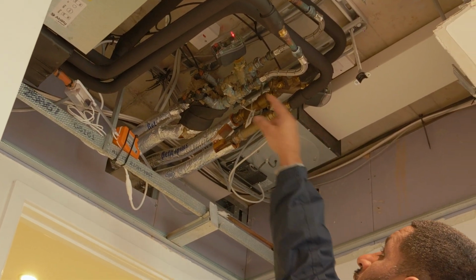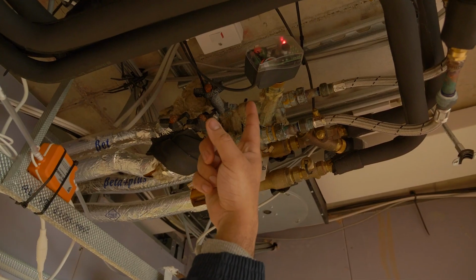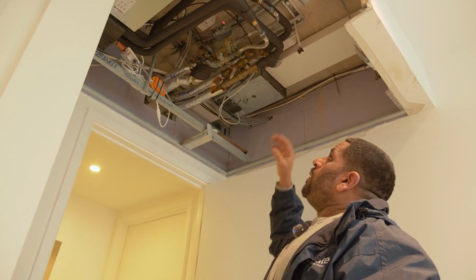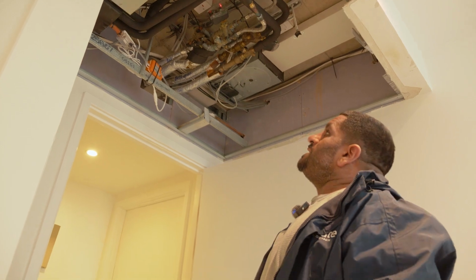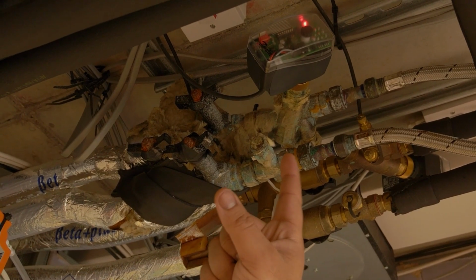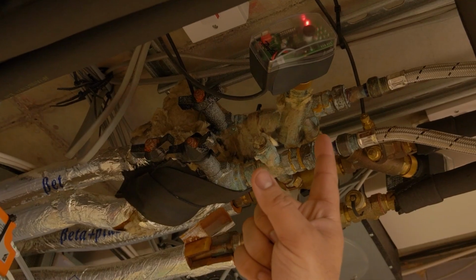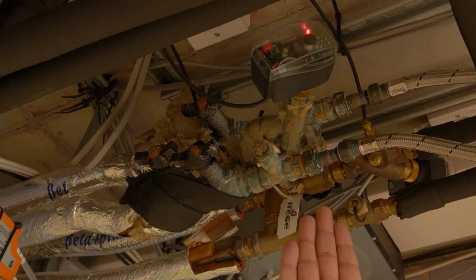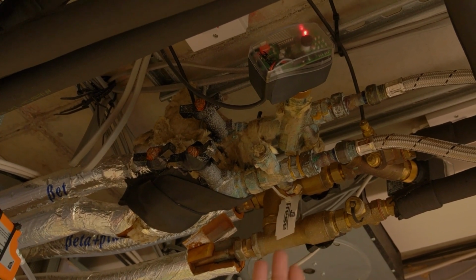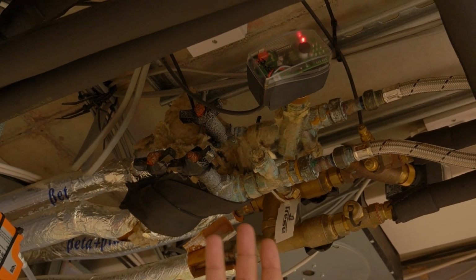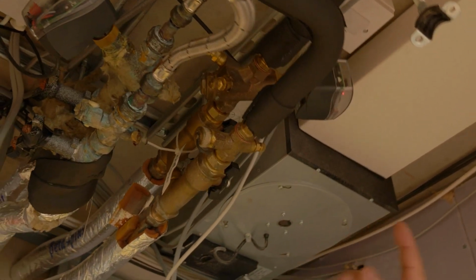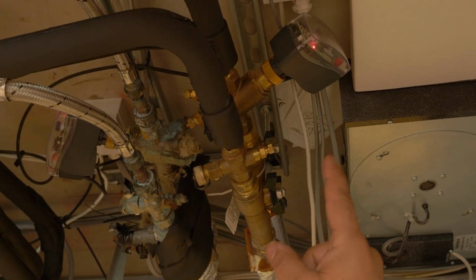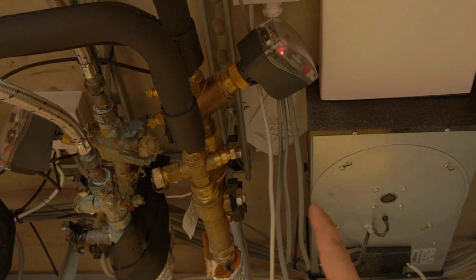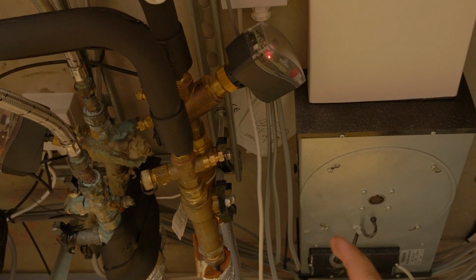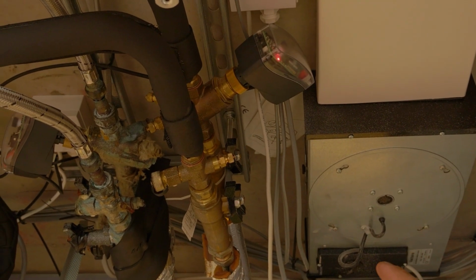We have 2 valves, as I mentioned earlier. One is the cooling valve and one is the heating valve, controlling the flow when required for whatever mode the client sets it in. These are Honeywell valves, and when this cooling valve is turned into cooling, you'll see through the cover there, the spindle will then drive the motor, the mechanical valve down and allow the correct amount of flow into the heat exchanger. The same principle will apply on this side with the heating valve. The red light means the unit is actually on, and then when you're driving the valves, these specific valves have a different set of LEDs which let you know whether they're driving down, driving up, or whether they have an error on seating the valve or finding their position.